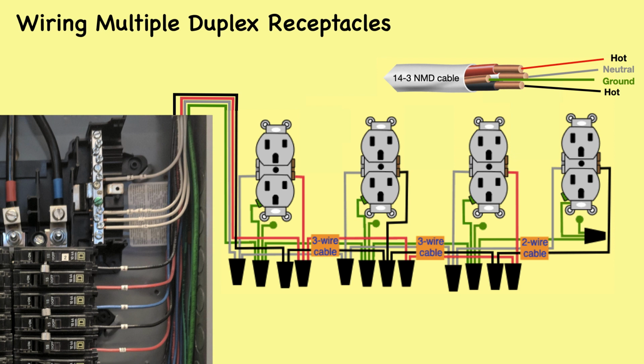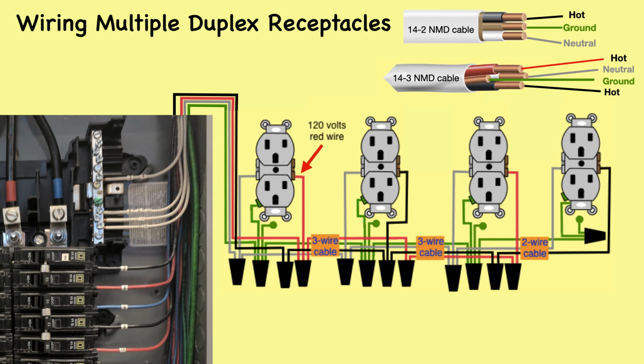Only a 2-wire cable is required for a run to the last receptacle. As you can see, the 3-wire cable red wire feeds 120 volts to one receptacle, while the 3-wire cable black wire feeds 120 volts to another receptacle. This allows for efficient use of cable wiring and protection, as a 3-wire cable can supply a total of 30 amps to various loads. This, however, only requires the installation of a double pole single throw 15 amp breaker back at the panel.